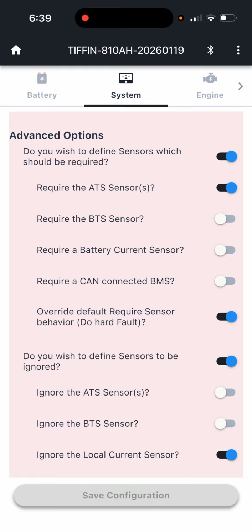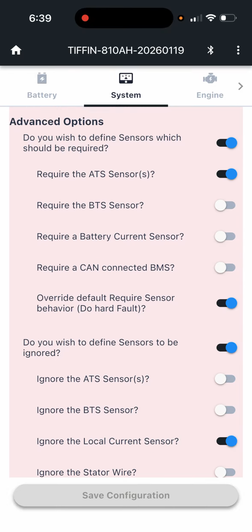Require a battery current sensor is disabled, and require a CAN connected BMS is disabled. This is to avoid confusing the CAN system with wrong information coming from Wakespeed, because by default Wakespeed tries to be the source for battery monitoring, and we don't want that in this situation.